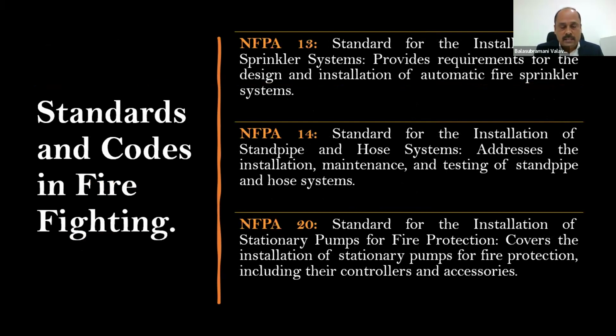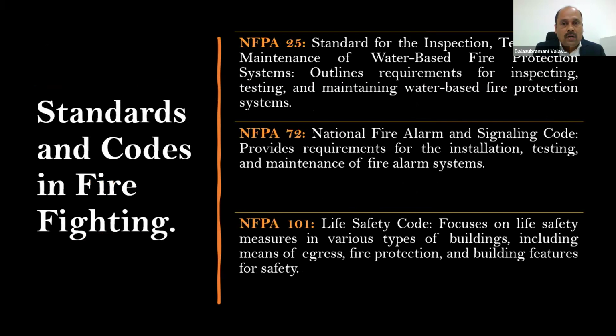For the pumps, controllers, and accessories, we will be covering the checklist in the later part of our slides: what all the parameters are, how you have to place them, what all things to be ensured, and how often the pump has to be tested. All those details are given in NFPA 20. Water-based fire protection is NFPA 25. And we all know wherever we go we will be seeing fire alarm systems and the signaling code, NFPA 72, one of the critical standards as far as NFPA is concerned. This has to be necessarily ensured. And most importantly, as safety professionals, NFPA 101 talks about safety measures of various buildings, including means of egress, fire protection, building features for safety, etc.